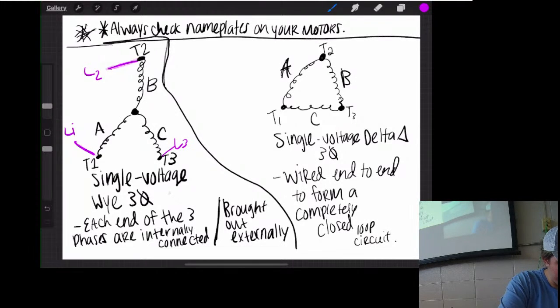All 3-phase motors are wired so the phases are connected together in either a Y or delta configuration. In a single voltage Y 3-phase, one end of each of the 3 phases is connected to the other phases, and the remaining end of each phase is brought out externally and connected to a power line, directly to your A, B, and C phase from the motor.